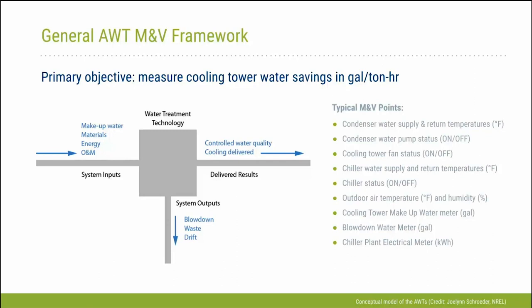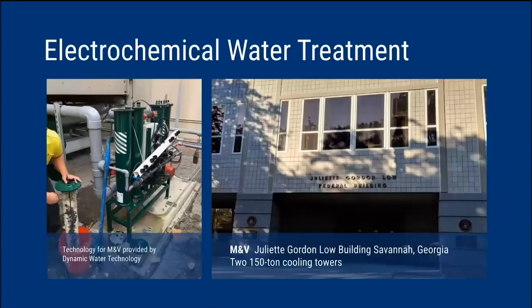And we do this over a period of time as a baseline where we study the basic system and get a baseline for how much water is being used based on energy usage or cooling load. Then we install the equipment and we take data for another period of months to compare. And we use some of the typical M&V points on the right, including load, outdoor air temperature, cooling tower status, water flow rates, and temperature flow rates, so we can compare apples to apples. Next slide.